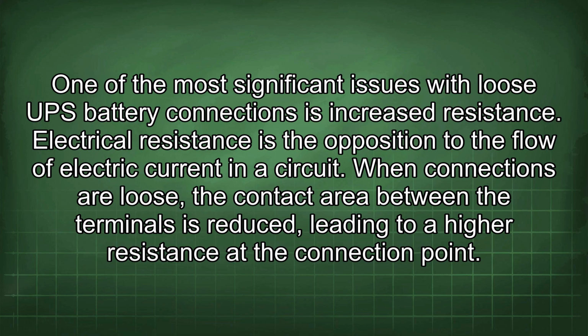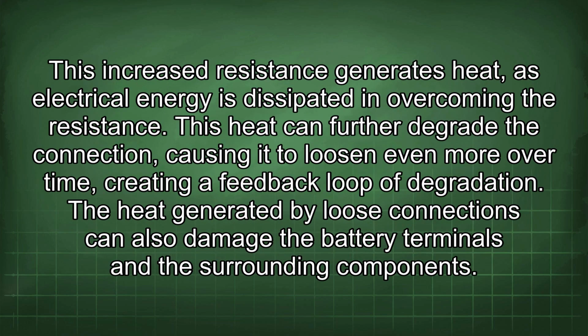One of the most significant issues with loose UPS battery connections is increased resistance. Electrical resistance is the opposition to the flow of electric current in a circuit. When connections are loose, the contact area between the terminals is reduced, leading to a higher resistance at the connection point. This increased resistance generates heat, as electrical energy is dissipated in overcoming the resistance.